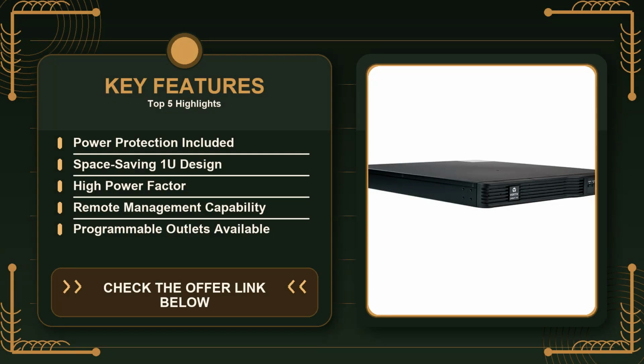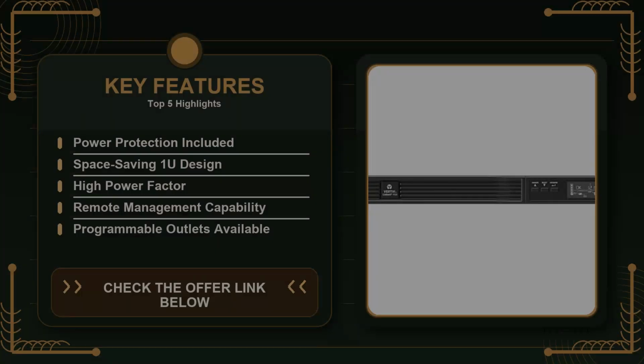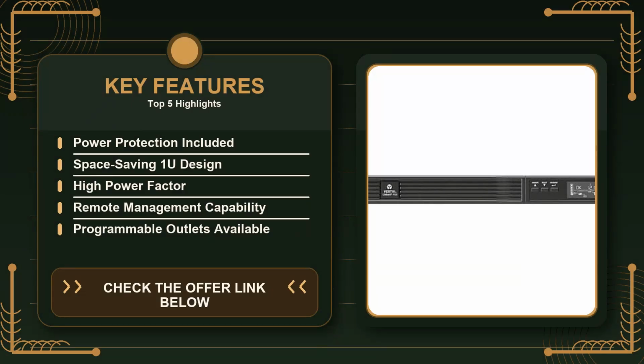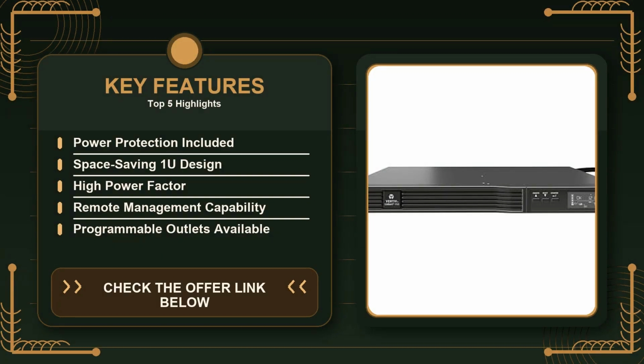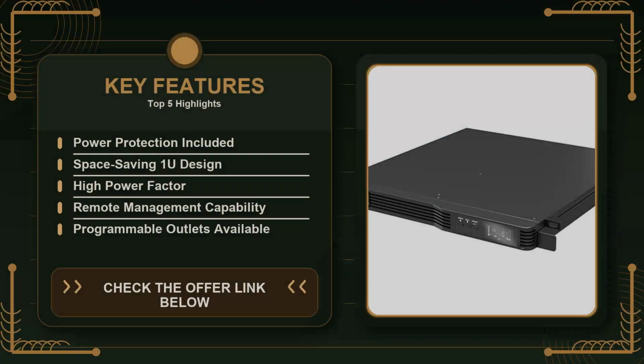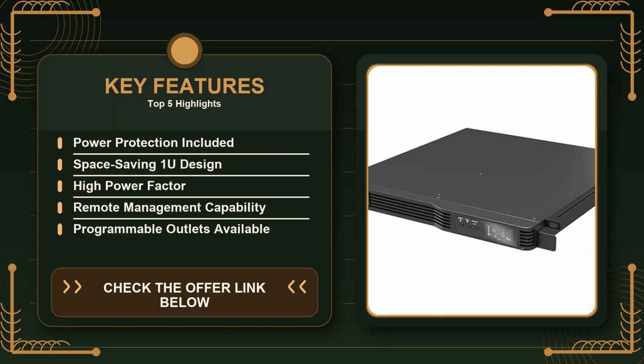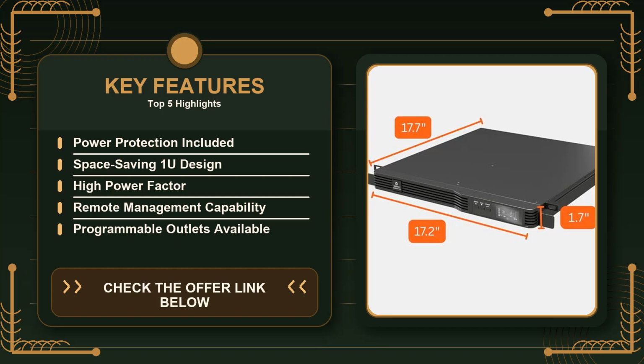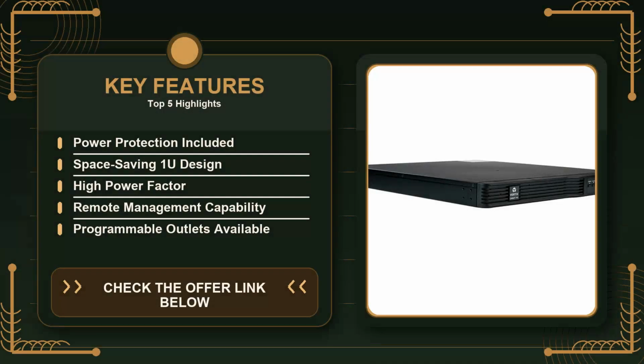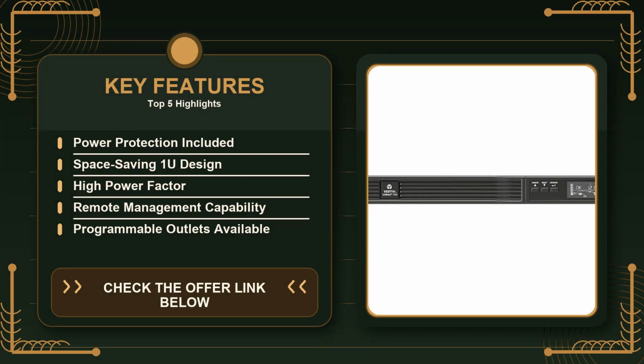Programmable outlets are another feature worth mentioning. The unit lets you set a delay on when each outlet powers up after the UPS restores utility power. This is handy in a rack where you want your networking equipment to come online first, then your servers, preventing a cascade of inrush currents that could trip the UPS's overload protection. I've seen this work well in small to medium businesses that stagger power-on sequences to avoid a sudden power spike when the mains return.